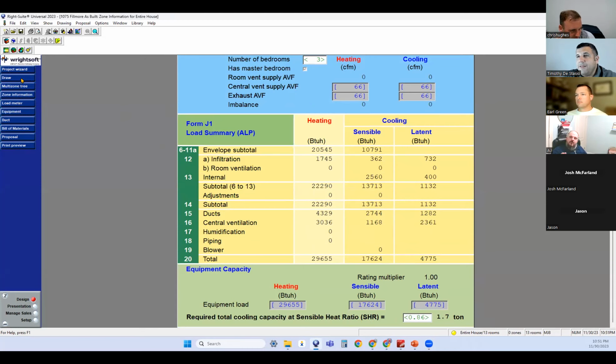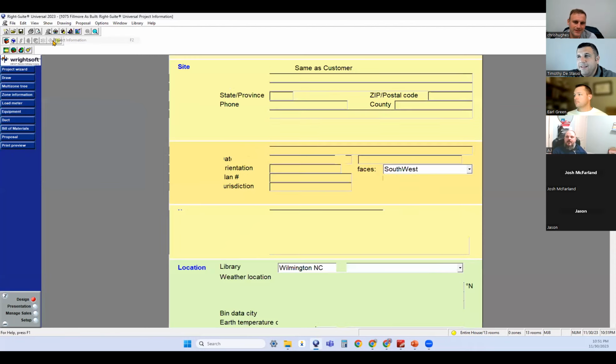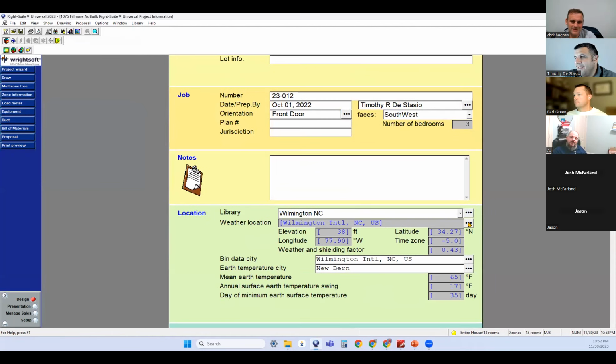Hold on. Speaking of that, did you show this to the builder? Yeah, I did. What do you say? Sit the builder down and explain all this to him, because he's the one that makes the changes. I know. But AJ, what you're not thinking is, for somebody to hear this for the first time who's not even in this trade, it will be so much to absorb. He'll never pick it up that way. Right. But look, just that in itself, you're putting 3.5 tons in your houses when all it needs is 2. Yep.